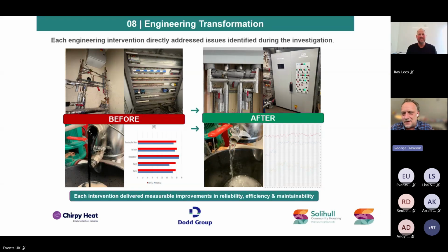As Aaron alluded to, and as some of our colleagues presented previously, key for us was the replacement of the BMS in the three energy centres to give us full controllability of the systems, both on-site and remotely. You can see from the pictures that the state of the closed circuit distribution pipework was in a very bad state of affairs, which led to a considerable number of outages in all of the schemes in question, leading to a very negative attitude toward the heat network from residents due to the interruption to heating and hot water service over quite a prolonged period.